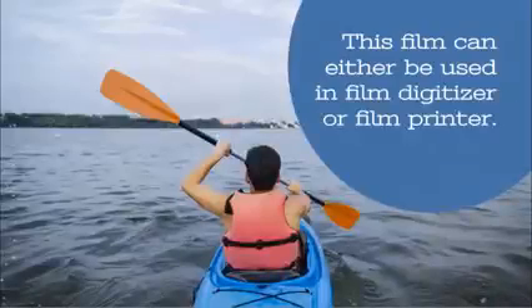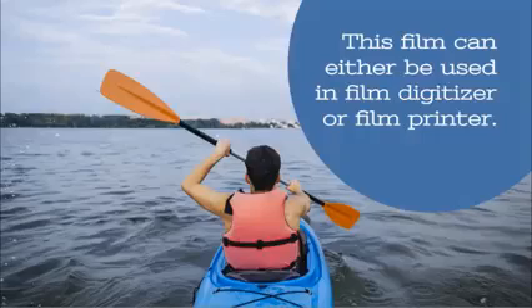This film can either be used in a film digitizer or film printer. A film digitizer creates a digital image from a hard copy or a radiograph. Okay, so when we say film digitizer, if you have a film, you just feed it into the film digitizer and it will provide you a soft copy of that hard copy film. And a film printer, of course, transforms the soft copy which is in the monitor into a hard copy or radiograph. Okay? So that is the difference from the film digitizer. From hard copy, you get a soft copy. With the film printer, from soft copy, you get a hard copy, such as a radiograph.